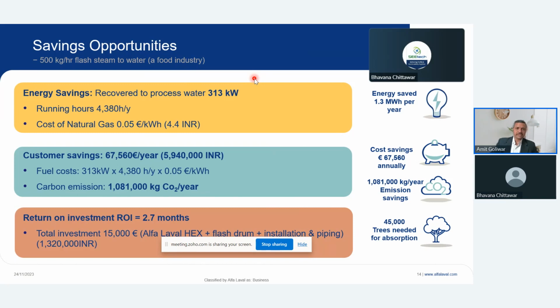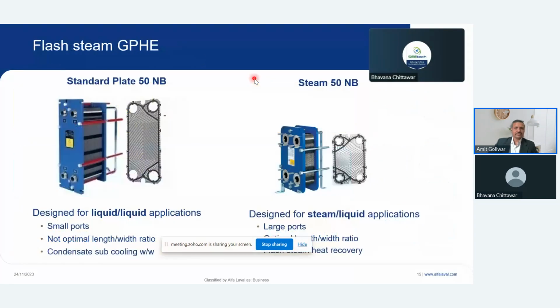Having said that, it's not the normal plate heat exchanger. The normal plate heat exchangers will be tall plates with smaller port size. But when it comes to steam, you need to have shorter plates with a bigger port size. Why? Because these are condensing duties. So the same plate heat exchanger is not suitable for condensing application and for sensible heat transfer.